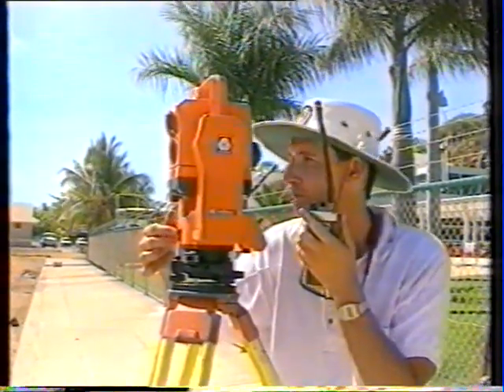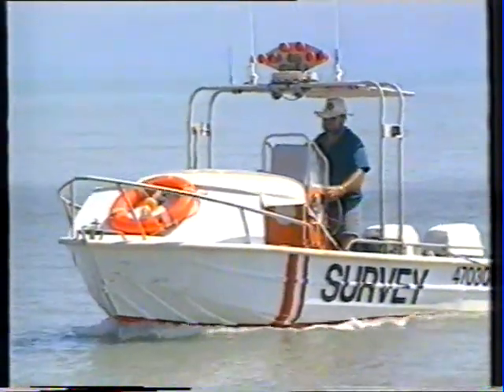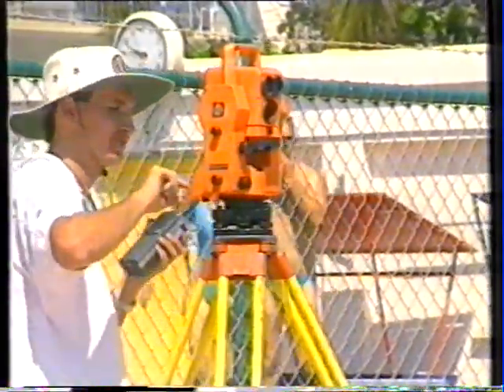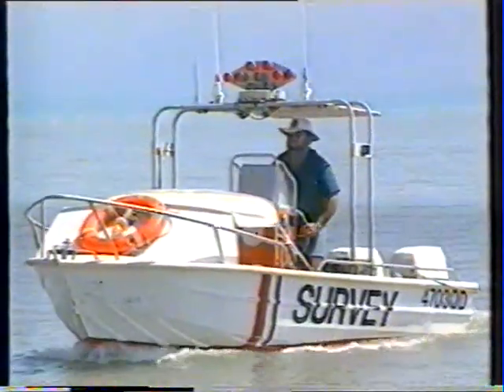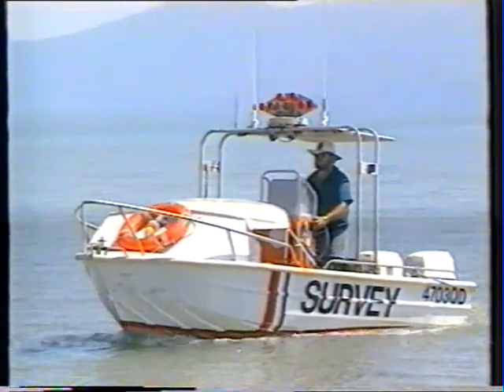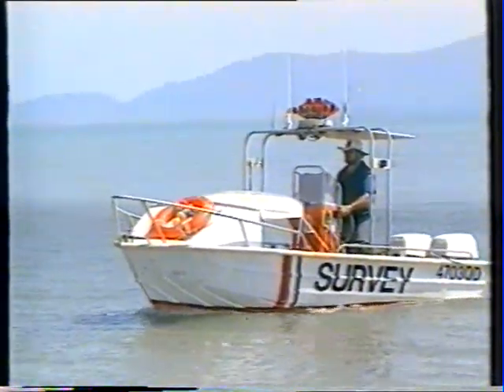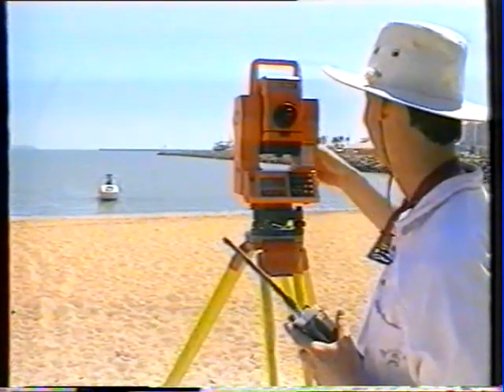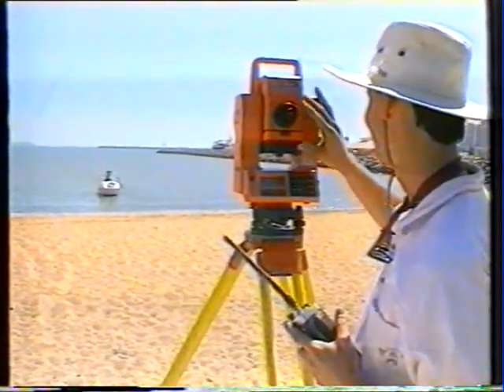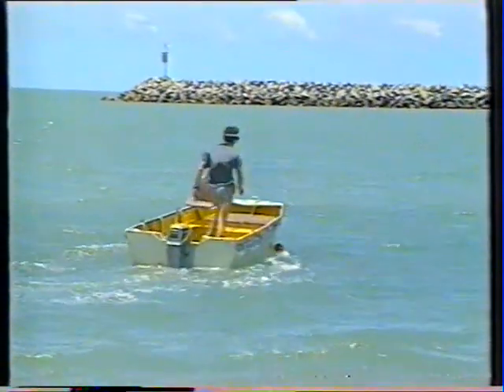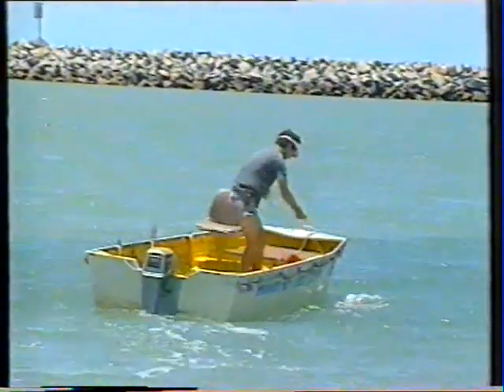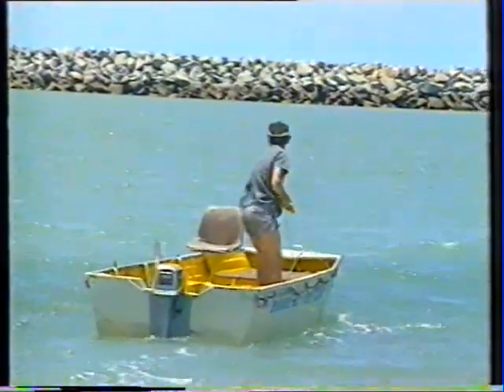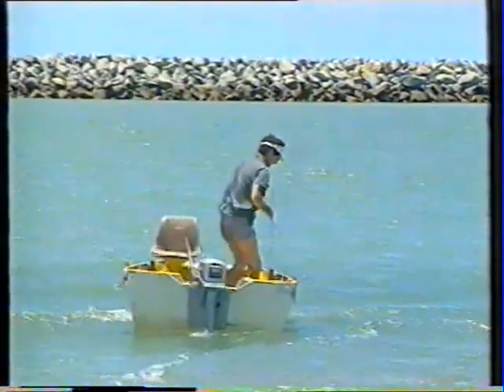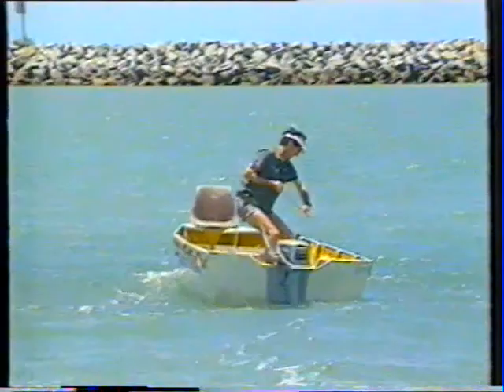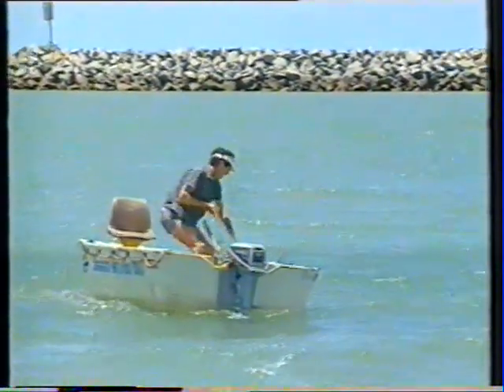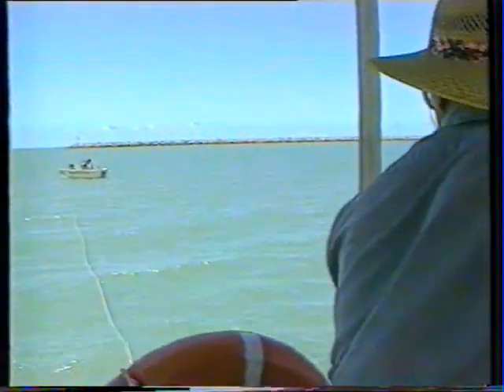Surveying the land ends for the proposed location of the new cable begins with precise accuracy. A plot is set and calibrated. 200 meters of the existing cable number 3 will have to be moved to enable the new number 4 cable to be laid between number 3 and the Marina channel, maintaining a clearance of 30 meters. 1,500 meters of the number 3 cable was buoyed to determine which sections needed to be moved over. The section of cable was excavated by divers using a suction dredge in zero visibility, raised, moved over and lowered to its new position. This section was then buried to a depth of 1.2 meters using a high-pressure water jet.